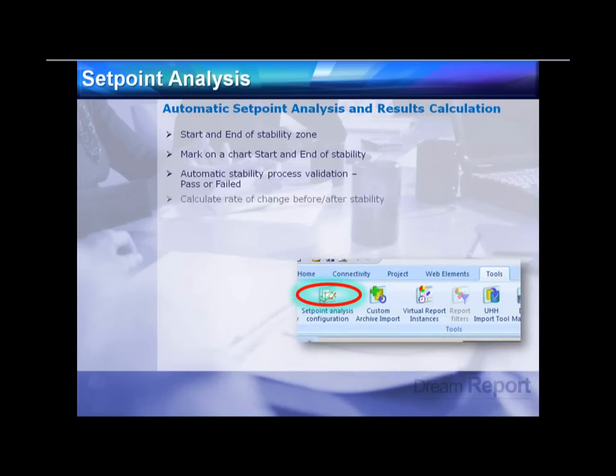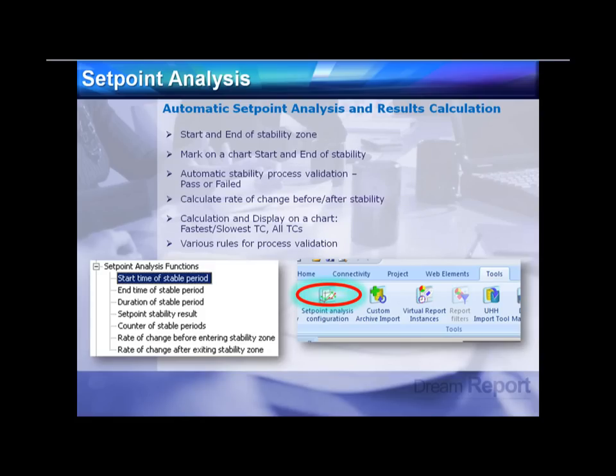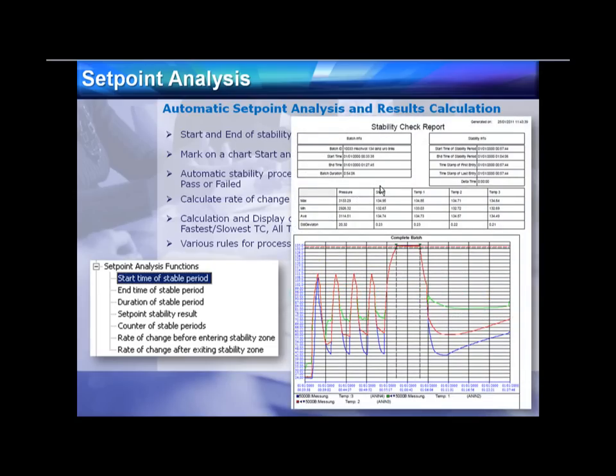There are industry-specific functional modules, such as setpoint analysis, applicable to heat treat processes or reactions. You define conditions for process stability — a specific temperature plus or minus a range, rates of change while ramping — and all of these are checkbox options with associated graphical objects. For example, a heat treat report showing target ranges, monitored thermocouples, and pass/fail results can be built without significant engineering effort because this functionality is built into the product.